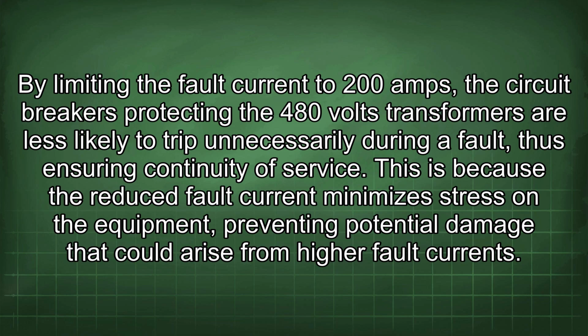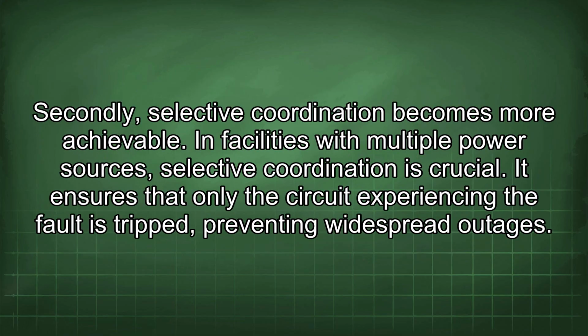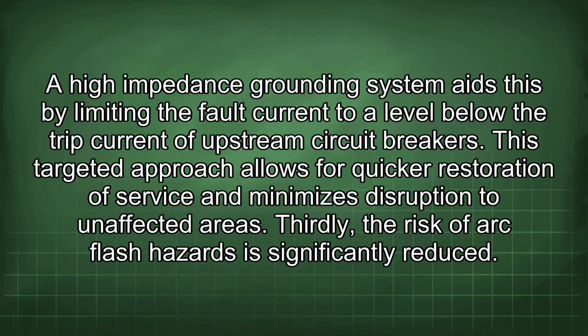This is because the reduced fault current minimizes stress on the equipment, preventing potential damage that could arise from higher fault currents. Secondly, selective coordination becomes more achievable. In facilities with multiple power sources, selective coordination is crucial. It ensures that only the circuit experiencing the fault is tripped, preventing widespread outages. A high impedance grounding system aids this by limiting the fault current to a level below the trip current of upstream circuit breakers. This targeted approach allows for quicker restoration of service and minimizes disruption to unaffected areas.